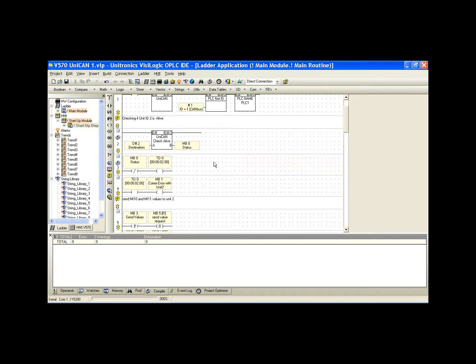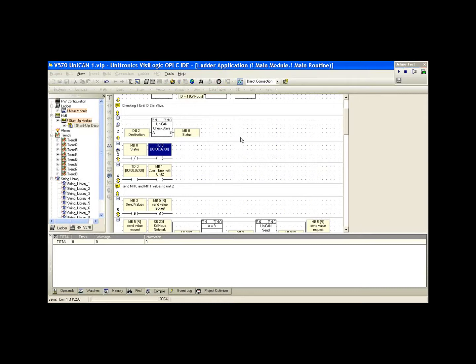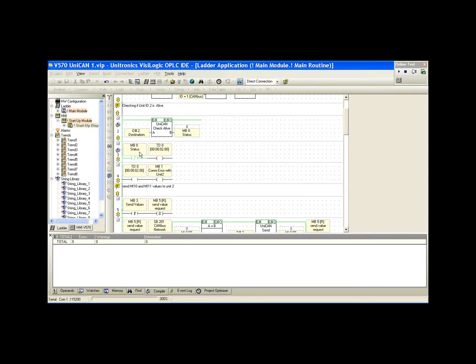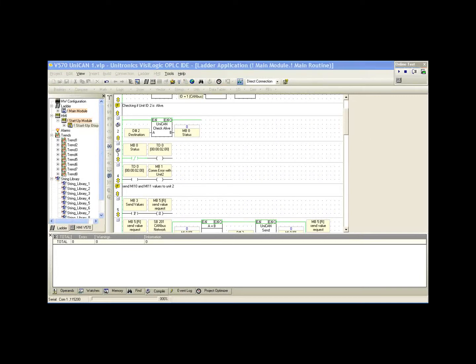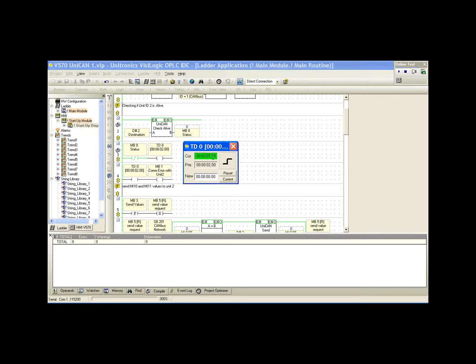We're using this with a timer network. TD 0 is a two-second timer. We'll go online and just look at this real quick. What we should see is that every half second, TD0 gets reset. Let's bring up TD0, it's on my other monitor. We see the countdown go from 2, and it never quite reaches 1.5 seconds. If I remove the cable, we'll see the countdown gets to zero.